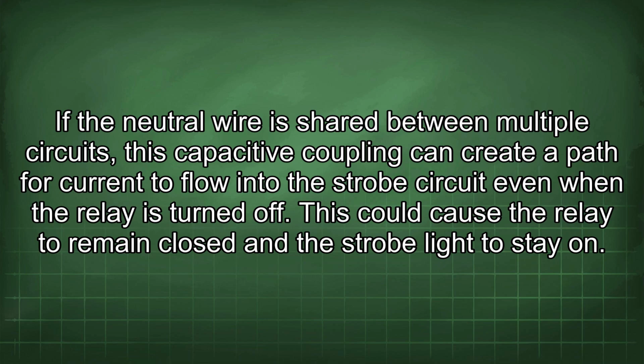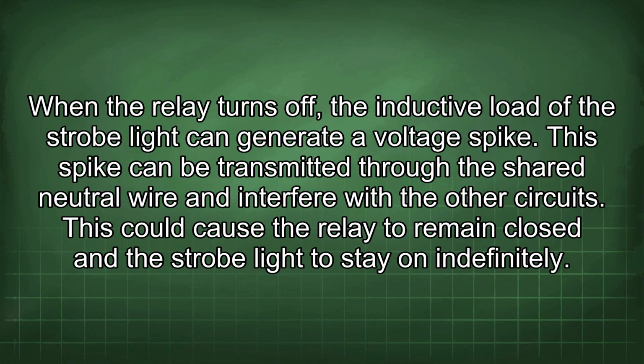This could cause the relay to remain closed and the strobe light to stay on. When the relay turns off, the inductive load of the strobe light can generate a voltage spike. This spike can be transmitted through the shared neutral wire and interfere with the other circuits. This could cause the relay to remain closed and the strobe light to stay on indefinitely.